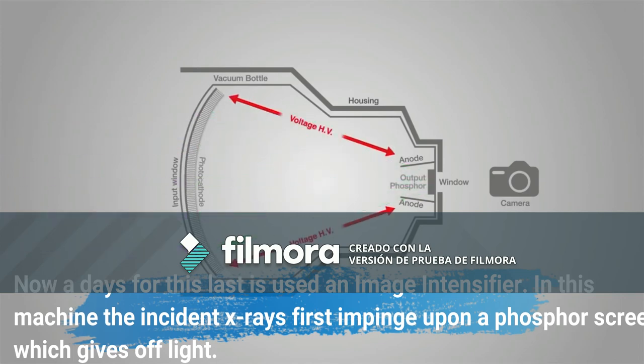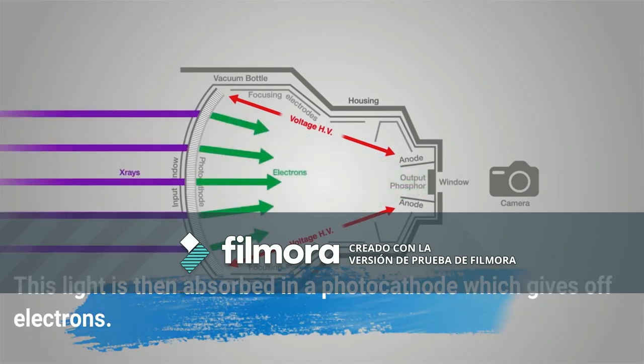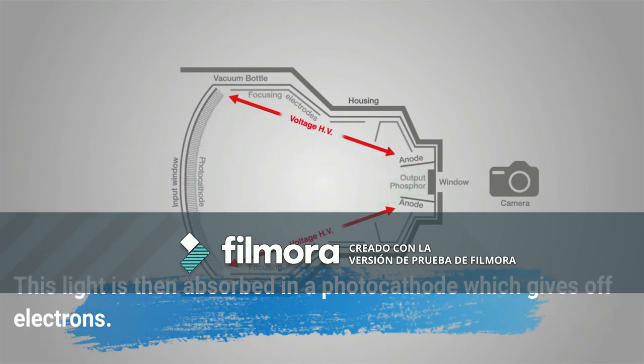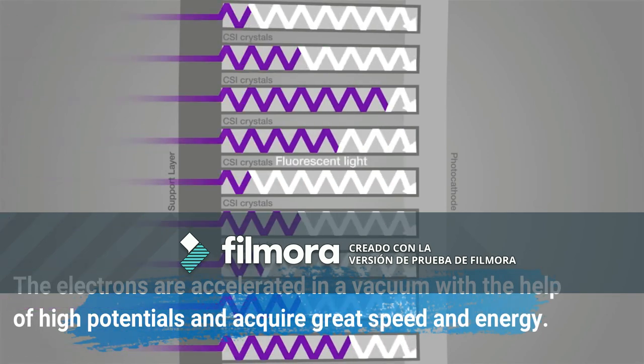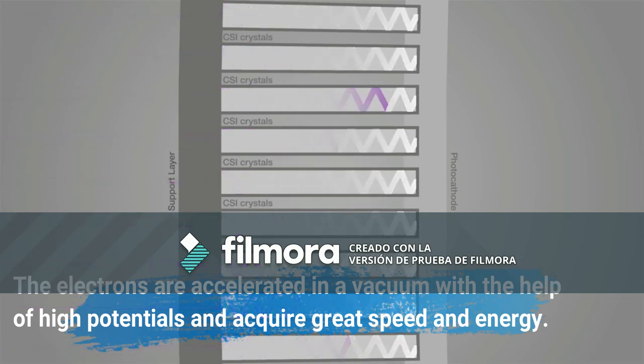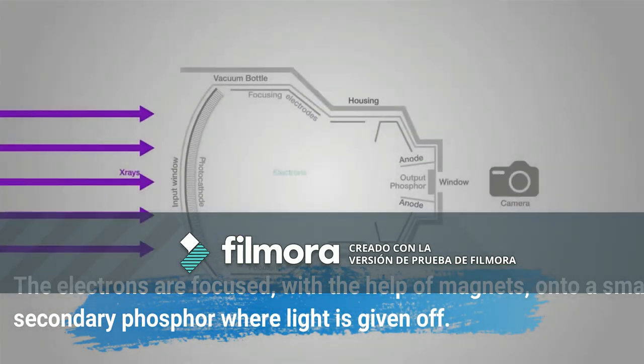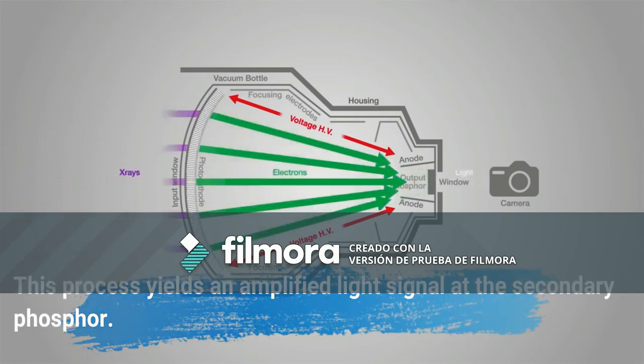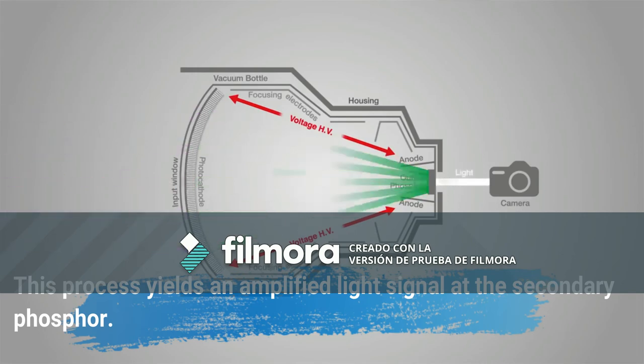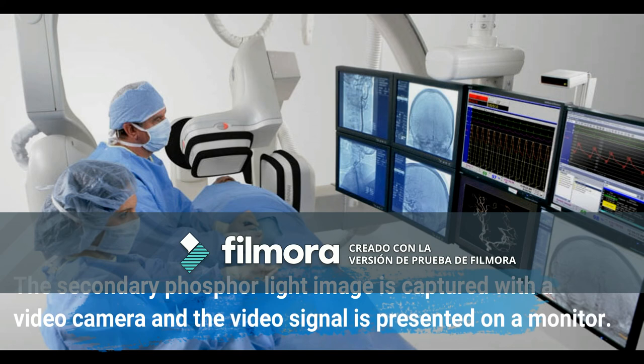Nowadays, for this an image intensifier is used. In this machine the incident x-rays first impinge upon a phosphor screen which gives off light. This light is then absorbed in a photocathode which gives off electrons. The electrons are accelerated in a vacuum with the help of high potentials and acquire great speed and energy. The electrons are focused, with the help of magnets, onto a small secondary phosphor where light is given off. This process yields an amplified light signal from the secondary phosphor. The secondary phosphor light image is captured with a video camera and the video signal is presented on a monitor.